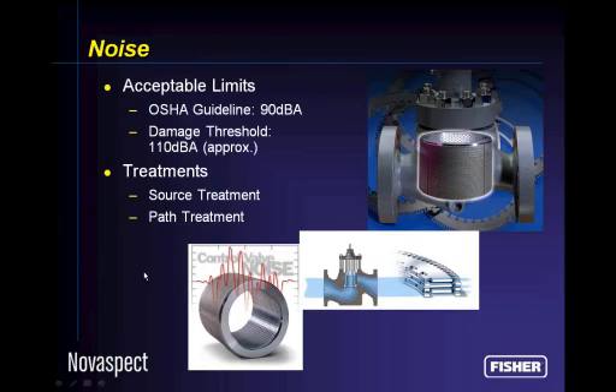In addition to all those four things we've discussed, somebody worries about noise. It's usually you. It's most often the valve manufacturer, but you've got OSHA laws, corporate practice, good neighbor policies. All of these things determine to what extent you need to attenuate the noise that's produced in a control valve or anywhere in your process for that matter.